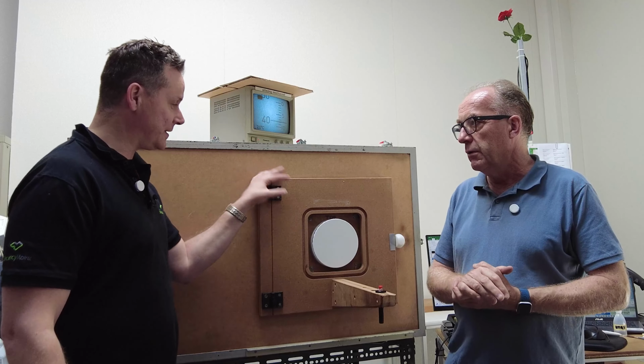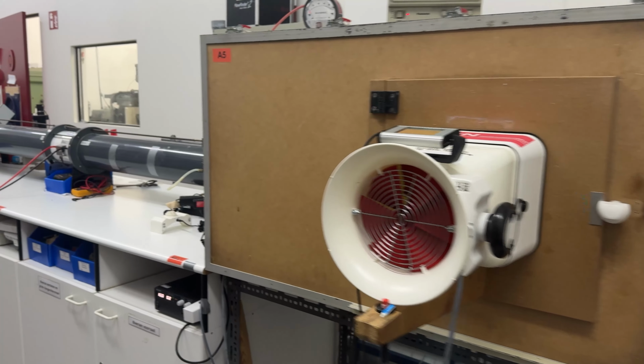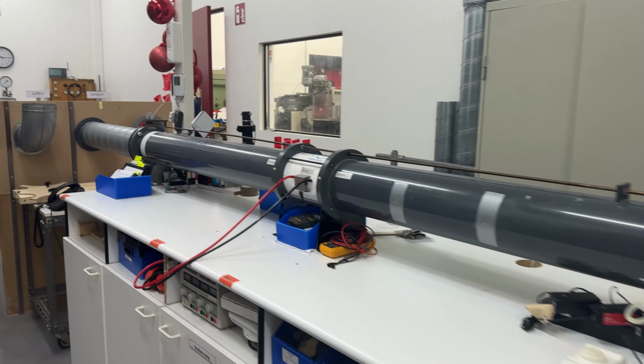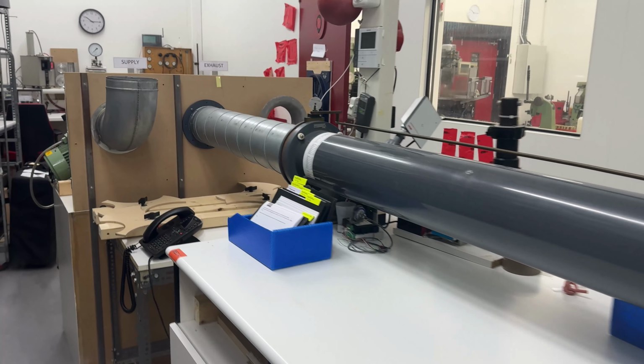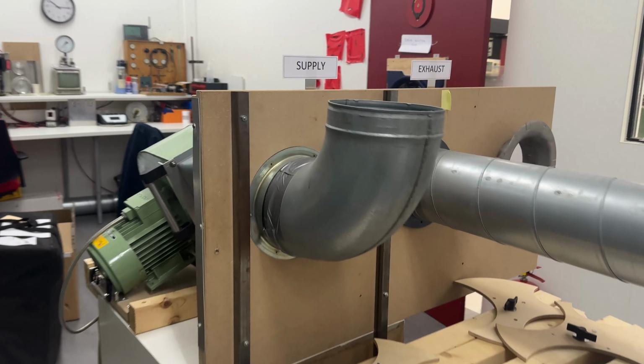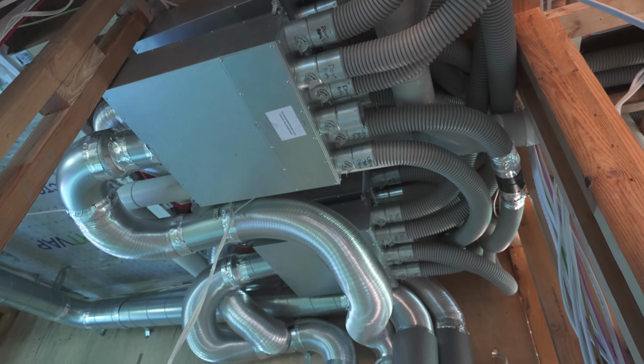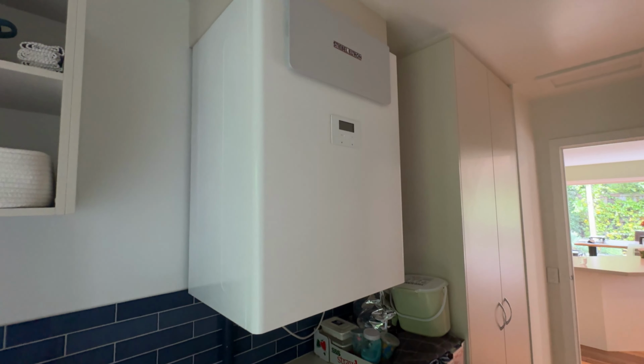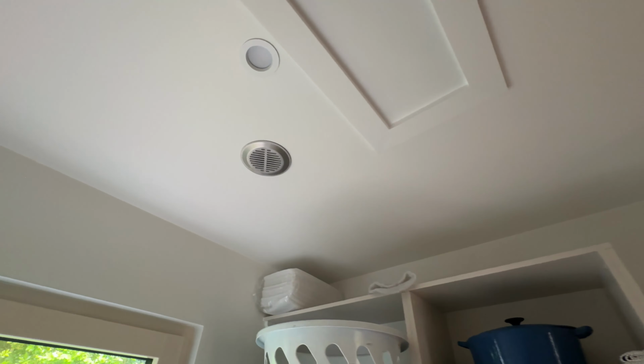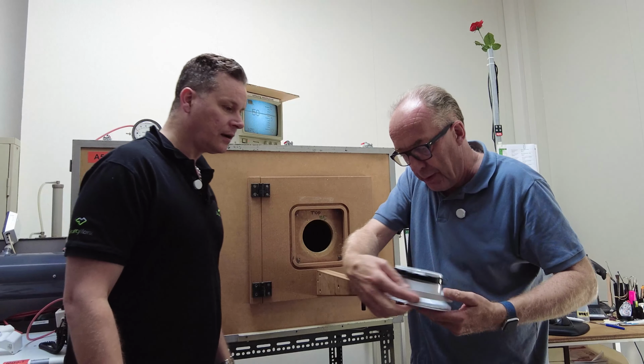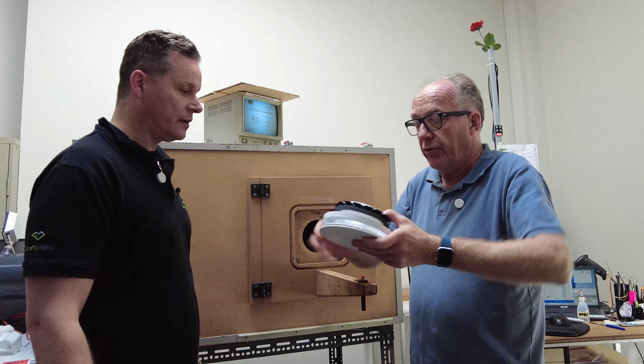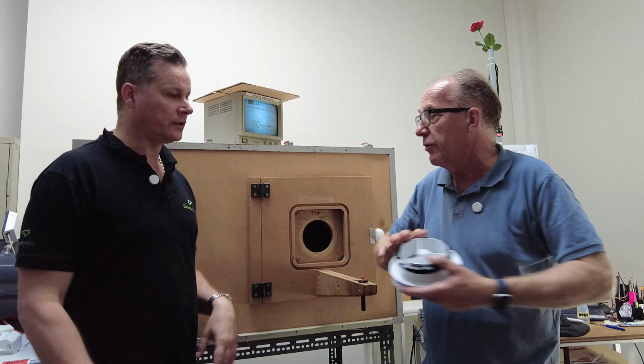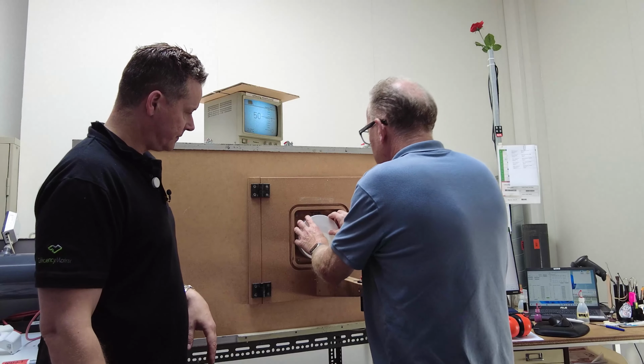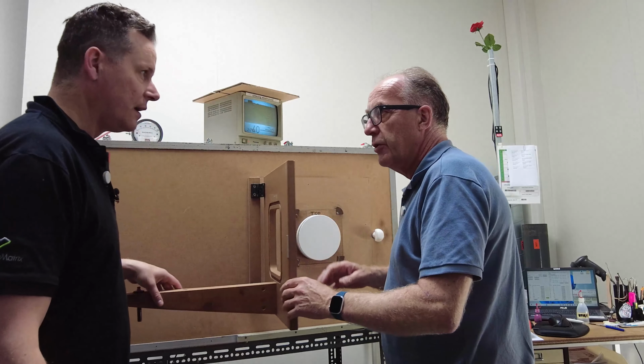Can we demonstrate here? This is a beautiful calibration rig that you guys have here on this effect, comparing it to just a normal flow hood. This is normally for residential, and often these kinds of grills are used when there is a heat recovery unit in the house. So you will be getting into really airtight houses, passive houses, where they use this. As you may see, on this grill the flow comes from around the side, so it throws the flow away to the side, to get a nice Coanda effect. And that makes it quite hard to get a good measurement.